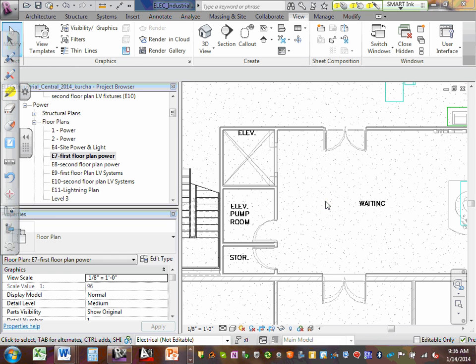if you have a fire alarm, let's say on the 2nd floor, that elevator must automatically recall to the 1st floor and stop. If you have a fire alarm on the 1st floor, that elevator must automatically recall to the 2nd floor and stop. So that's primary and alternate recall. In multi-story buildings, which you're not dealing with here, greater than 2 stories, generally your primary recall floor is the 1st floor, and your secondary recall floor is the 2nd floor. Okay.